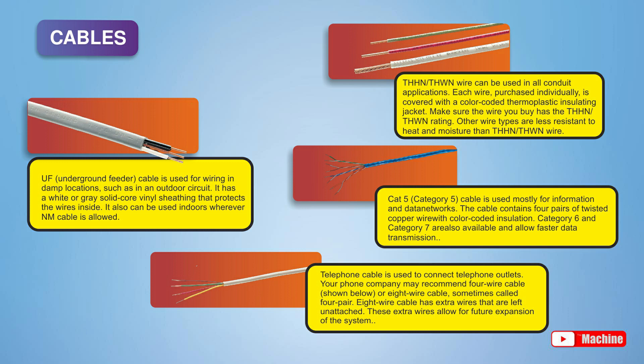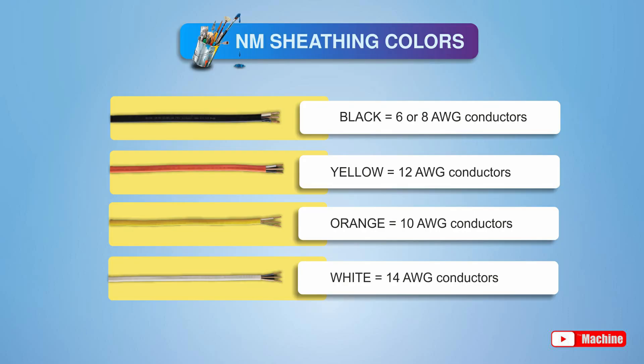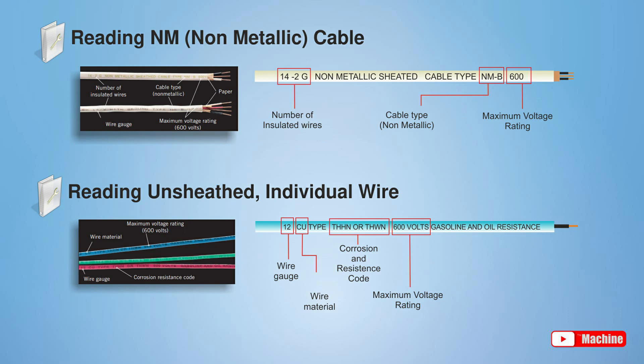Telephone cable is used to connect telephone outlets. The PVC sheathing for non-metallic cable is coded by color, so wiring inspectors can tell what the capacity of the cable is at a glance. Non-metallic cable is labeled with the number of insulated wires it contains; the bare grounding wire is not counted. Unsheathed individual wires are used for conduit and raceway installations. Wire insulation is coded with letters to indicate resistance to moisture, heat, and gas or oil.